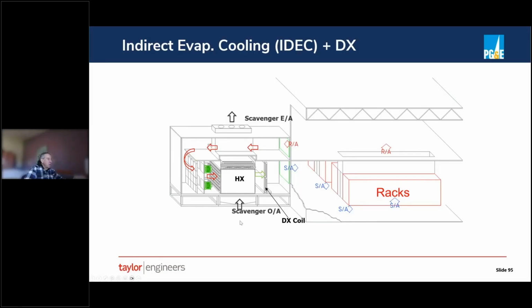And then, as I said, the heat exchanger has an outside air side that's pulling outside air. It's spraying water over the heat exchanger. And so basically that can cool the recirculated air down. And then to supplement that, there's a DX coil that provides additional cooling if the heat exchanger can't do the full thing. And the big advantage here is that we're not bringing in any outside air. So we don't have to deal as much with particulates and filtration and space pressurization because it's basically a sealed space.